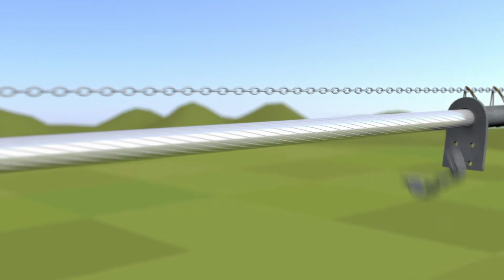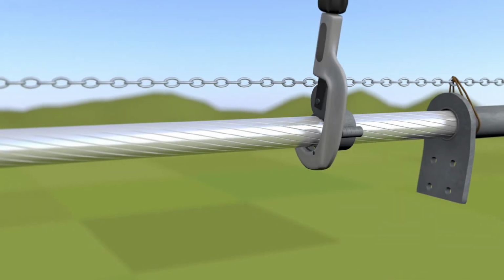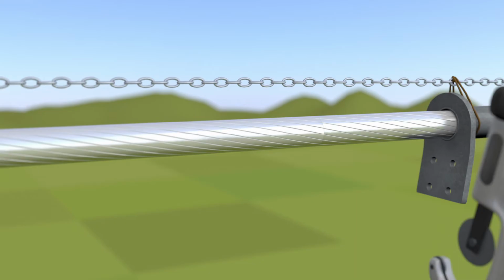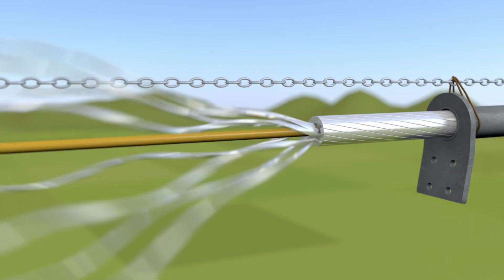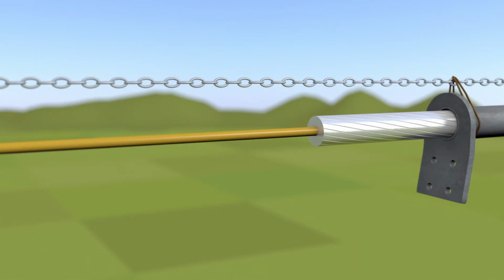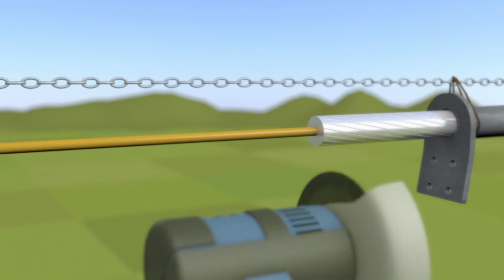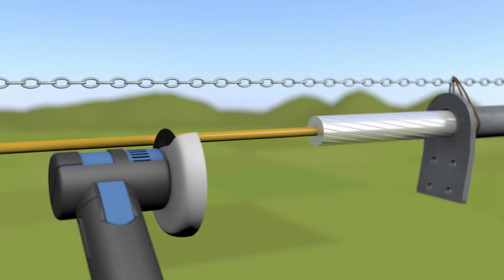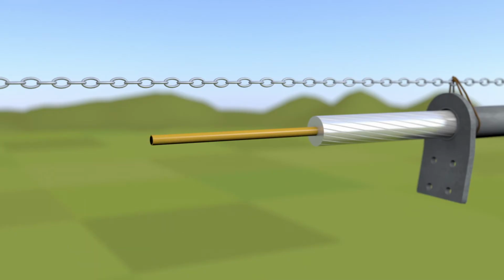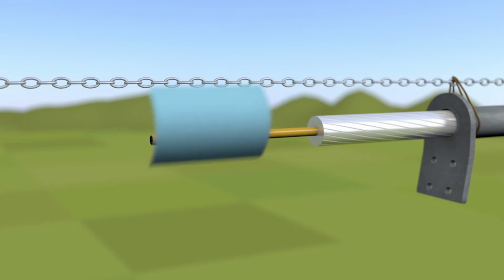The aluminium layers are trimmed to reveal approximately 1 meter of core. Once again, the inner wires should be notched only and removed manually by bending and fatiguing. The final cut of the core is then made using an appropriate cutting device in preparation for final inspection and assembly. We use a cloth to clean the core to remove oils or residue from the stranding process.